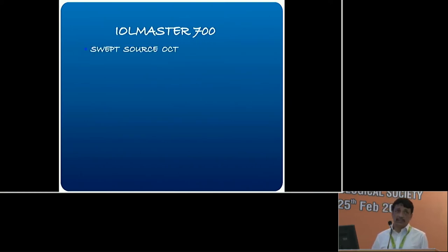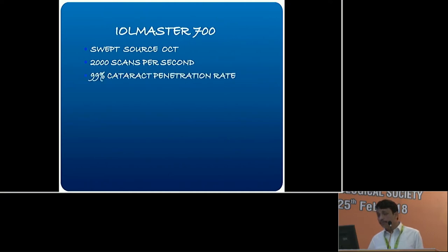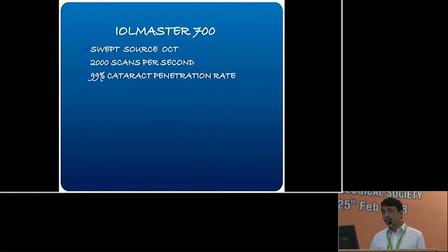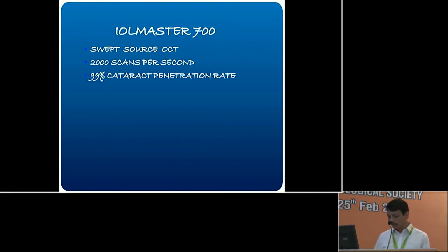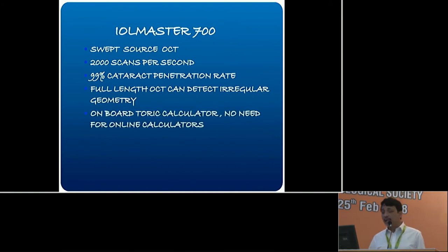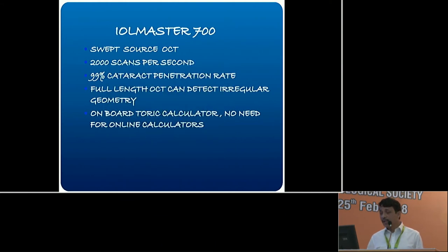The IOL Master 700 was launched in 2014 — the 500 was the initial version. The 700 uses OCT technology, calculating 2,000 scans per second, which is astonishing. Zeiss claims a 99% penetration rate, meaning dense PSCs and nuclear sclerosis can be managed. The OCT can detect irregular geometries such as lens tilt before surgery. It also has an onboard toric calculator, so no online calculator is needed. The 700 seems a very, very good option.